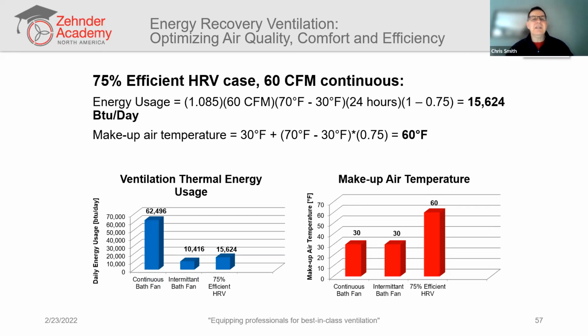All right, let's say we use an HRV, and the HRV has 75% efficiency, 75% energy recovery, sensible recovery efficiency. Well, the energy usage of that ventilation solution is almost 16,000 BTUs per day. So it's more than an intermittent bath fan that's only running 2 hours a day, but it's way less. It's only a quarter of using that bath fan 24/7 to achieve the same ventilation rate.